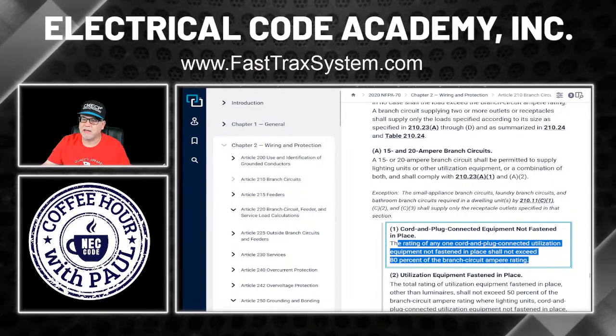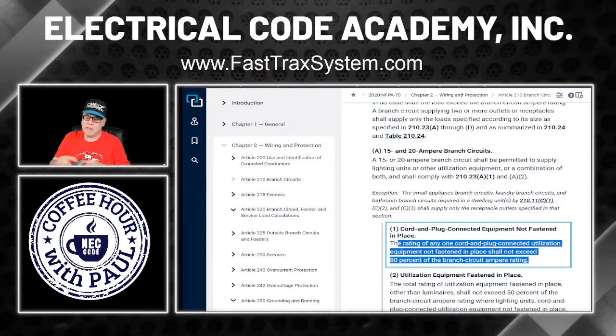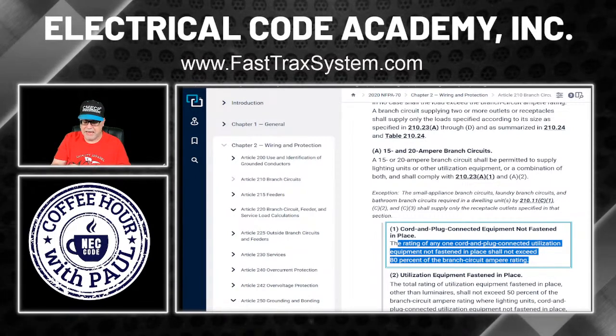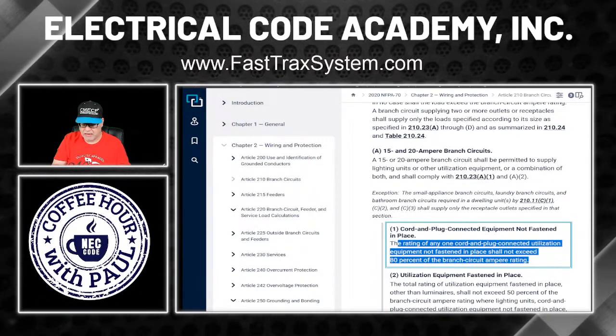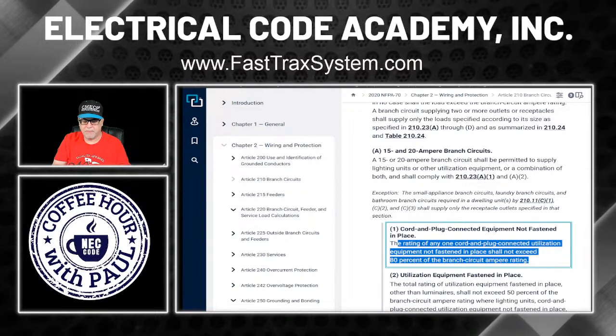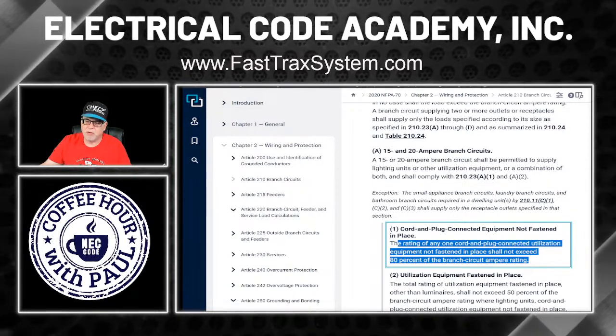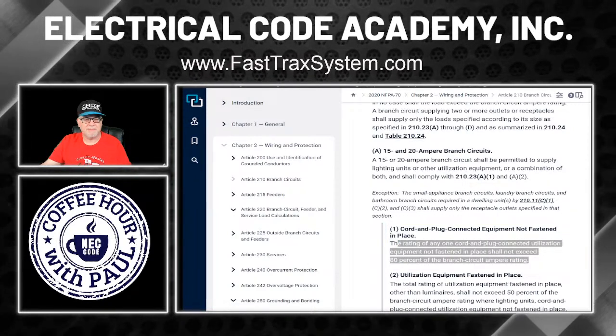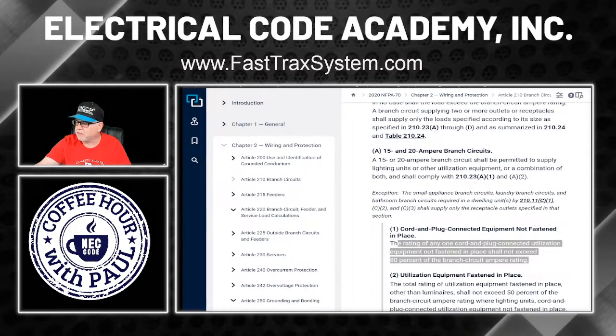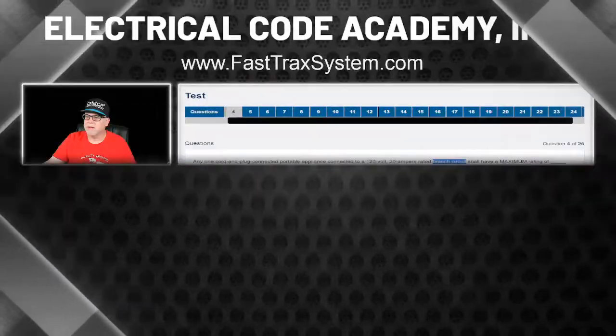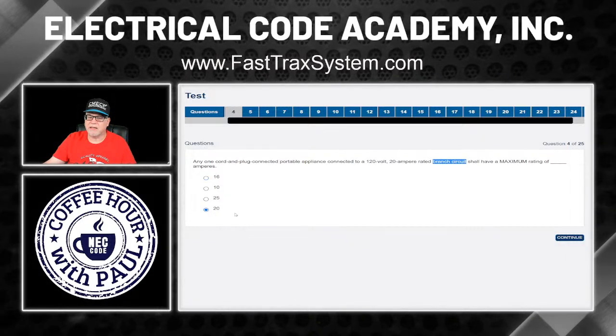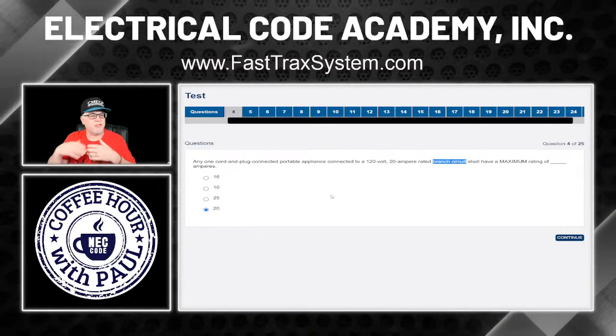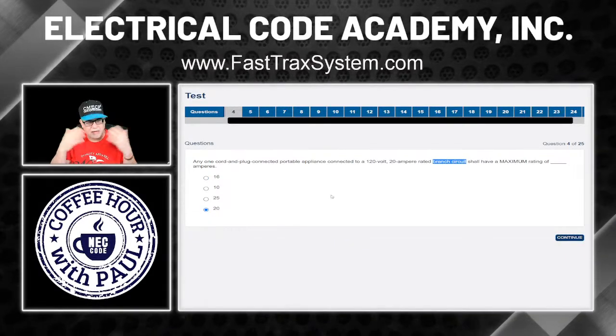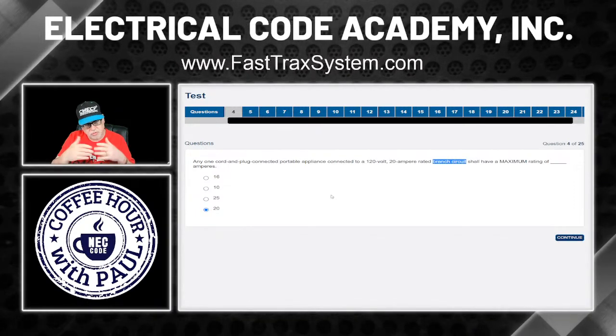Okay, so we were ready to click this 20. But reading that, I'm going to do 20 times 80%, and that is 16. So I'm going to choose 16. Oops, got to bring you back to me so you can see what we're doing here. We originally clicked 20 because we're thinking the branch circuit rating is 20 amp, and you can put 20 amps on it.